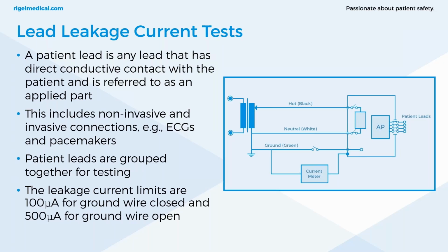In earlier revisions of NFPA 99, it did state that each individual applied part to ground must be measured. However, in the last two editions, including 2021, patient leads are grouped together and measured as a whole. These are always shorted together and just measured as the sum of total leakage. Testing should be carried out using this circuit on the right with the device powered on. The leakage current limits are 100 microamps for the ground wire closed and 500 microamps for the ground wire open. As in this example, we've got the ground open, but the fault conditions will be introduced by the safety analyzer.